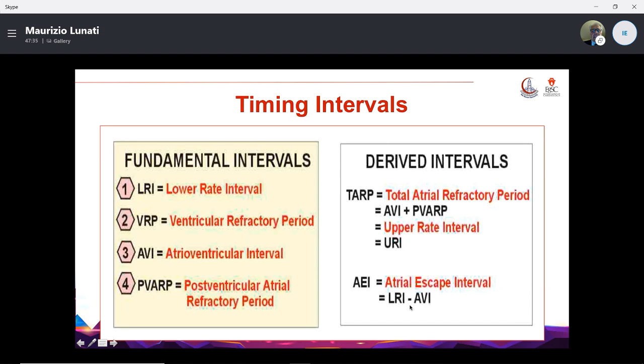But we also have derived intervals, which are the TARP, the total atrial refractory period, which is the sum of the AV interval and the postventricular atrial refractory period. Why is this so important? Because it defines the upper rate interval, the maximum rate that the device could reach in a dual chamber mode. Another derived interval is the atrial escape interval, which is the lower rate interval minus the AV interval.